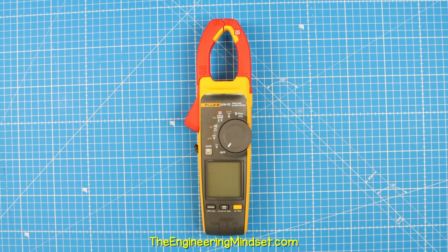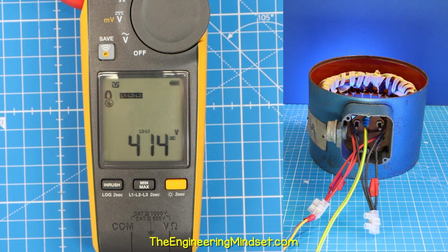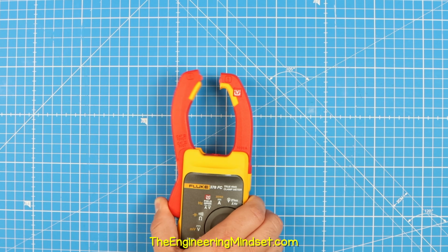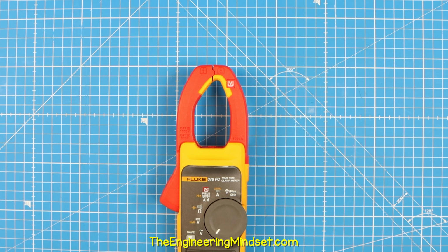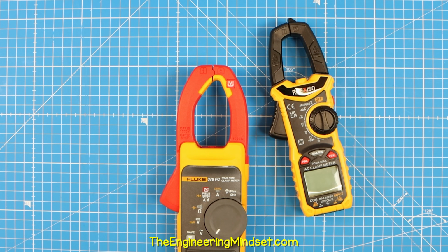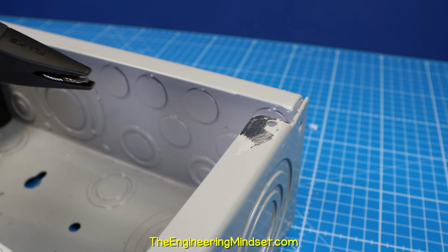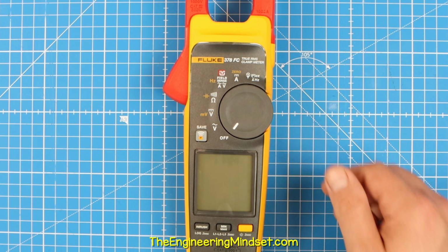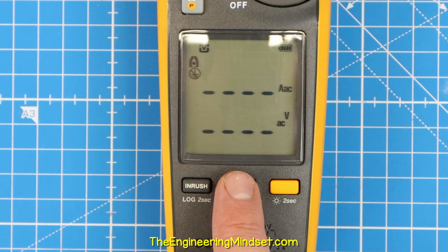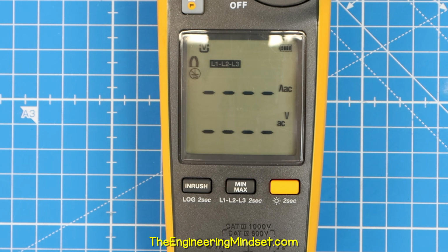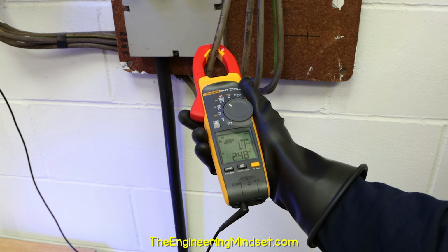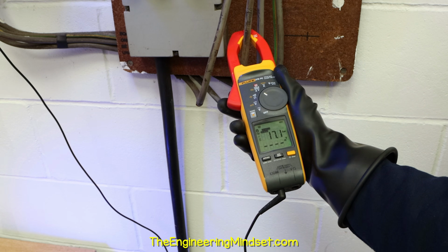By using the Fluke 378FC, we can check the voltage and current of a 3-phase system using just the clamp. Most other devices will not have this feature. Insert the ground lead and attach the clamp to a grounded surface. Then select the Field Sense function. Hold the min-max button for 2 seconds until the screen changes. Then clamp around phase 1, then phase 2, and then phase 3.